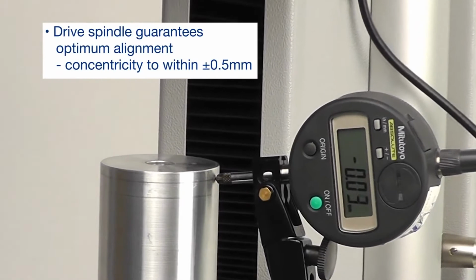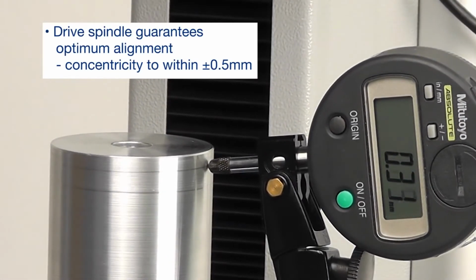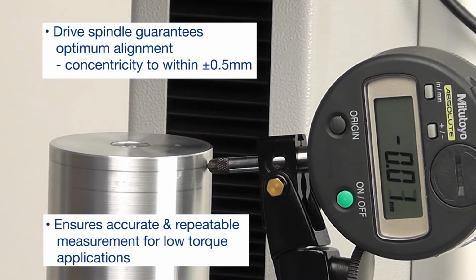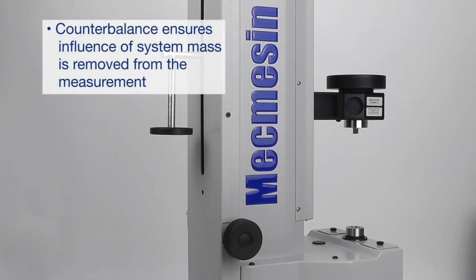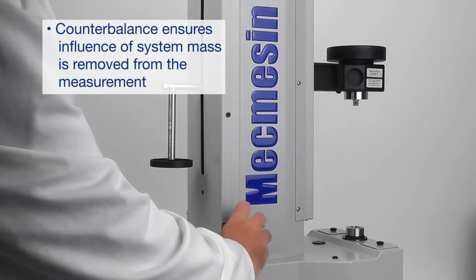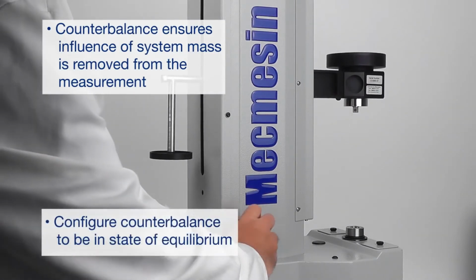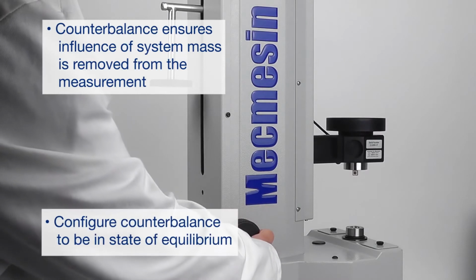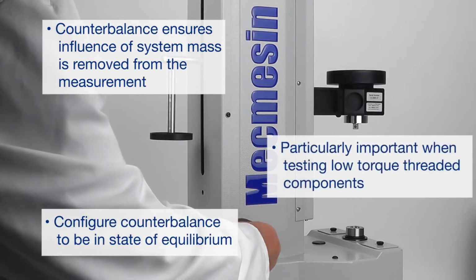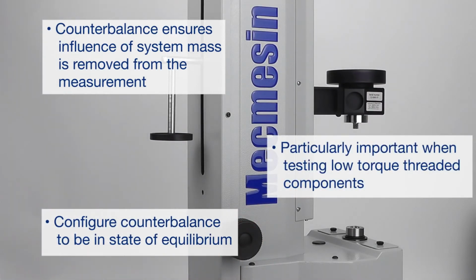The drive spindle is aligned to within half a millimetre, which ensures low torque measurements can be made accurately and repeatably. A counterbalance system removes the influence of the system mass from the measurement, which is particularly important when testing low torque threaded components.